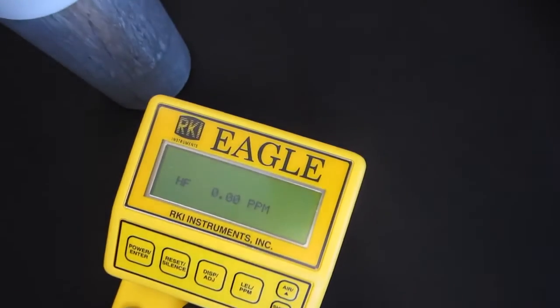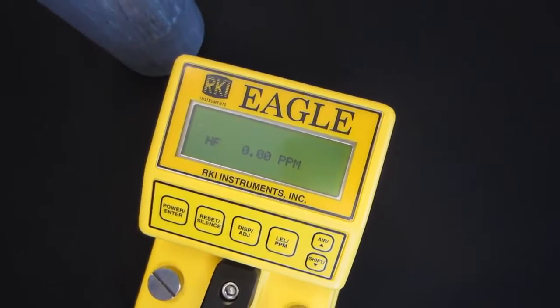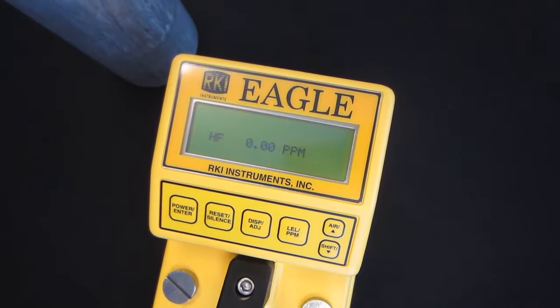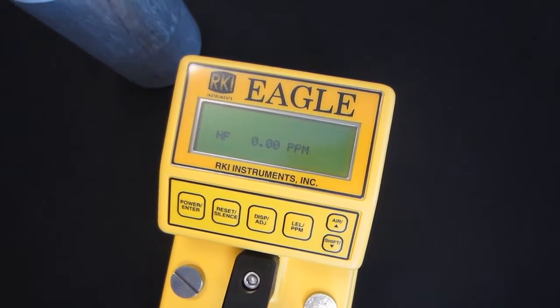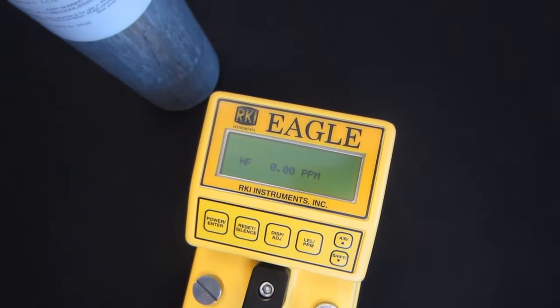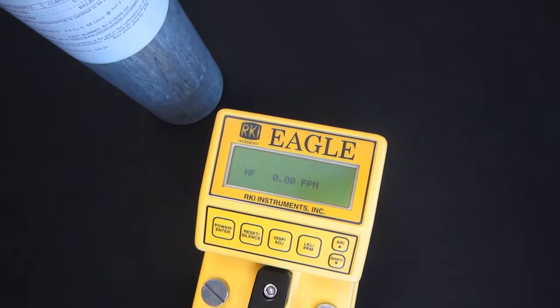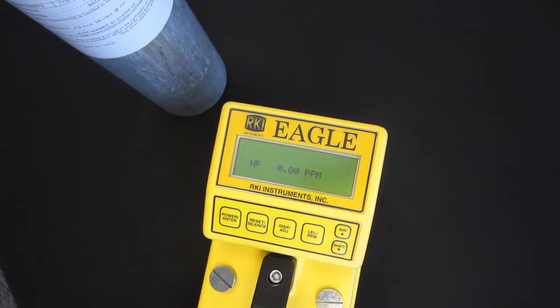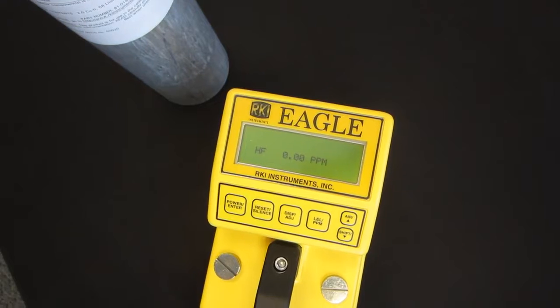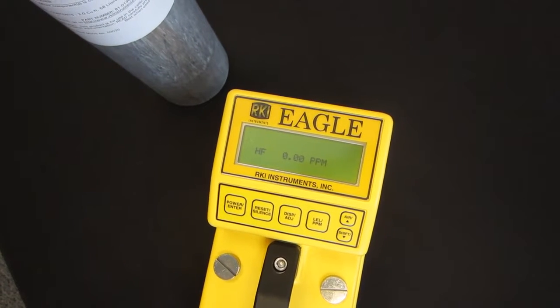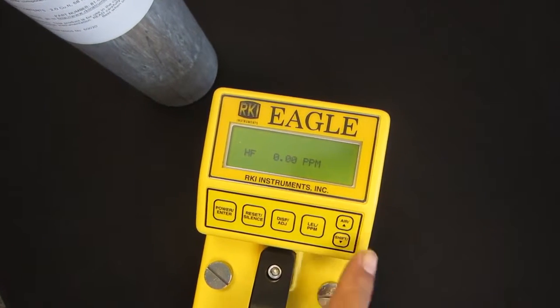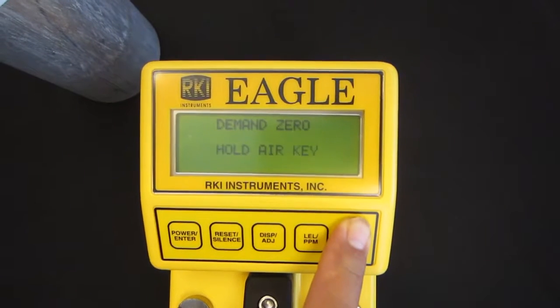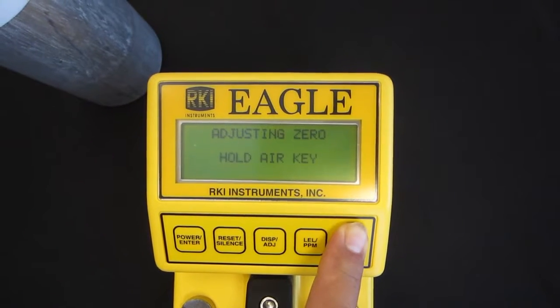If you do this on a daily basis, or at least on a frequent basis, a few times a week, or whatever frequency protocol you want to do, before you apply the gas to the unit, you want to make sure you have the unit in a clean air environment. It's been on for a few minutes, let's say at least 5 minutes, and is warmed up. At this point, we're going to press and hold down the air button, and it'll say demand 0, adjusting 0, hold air key.